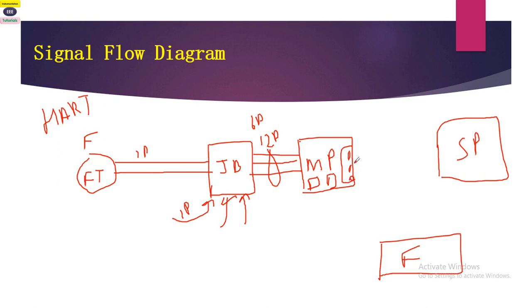This board is directly connected to the IO card installed in the system panel. The IO card is connected to the controller through buses or other connections. The controller takes actions based on the logics configured in it to actuate the final control element. So the signal flows from field → junction box → marshaling panel → system panel, where the controller gives the command to actuate the control valve or final control element.